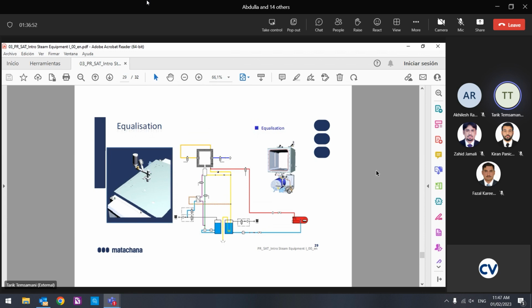No filter, because if the filter is choked, the air quantity taken in is very low and it takes a long time. So they remove it. That's very bad, because it's an antibacterial filter, it's taking the air from outside. And if the area around the machine is not clean, all these things come to the load directly after the sterilization.